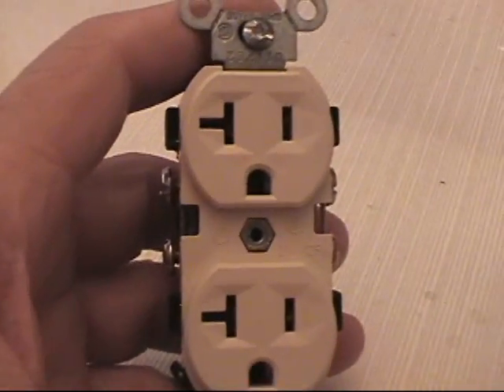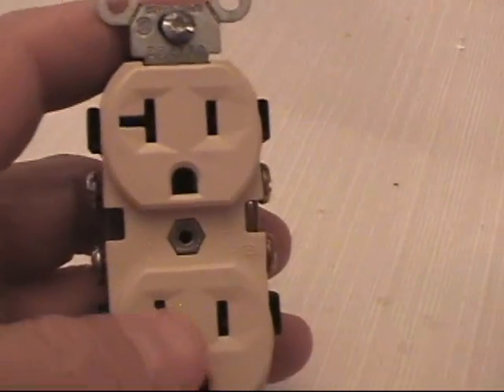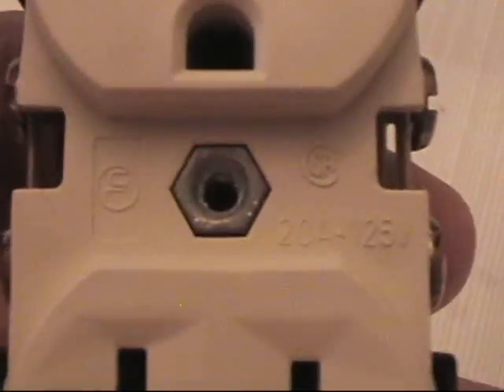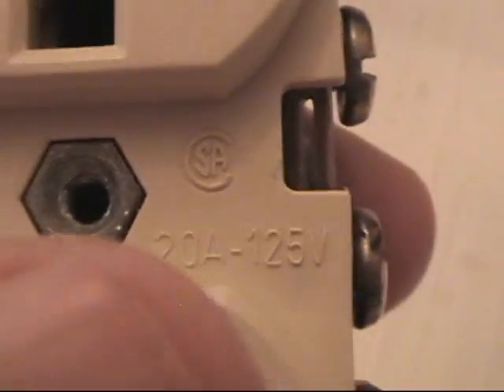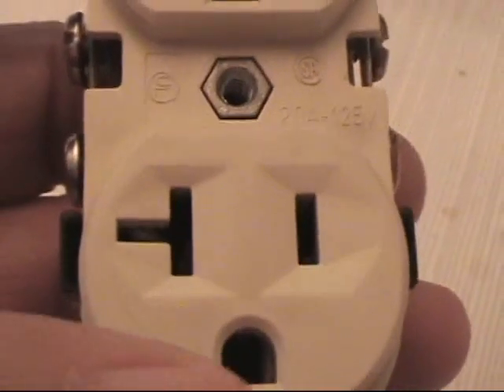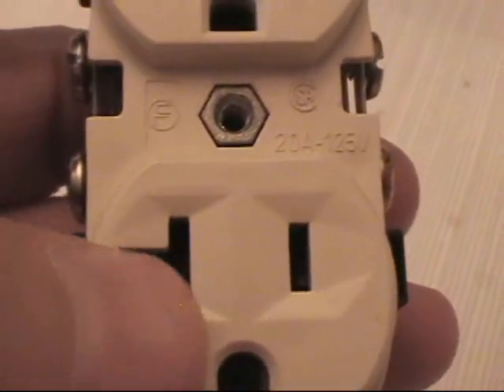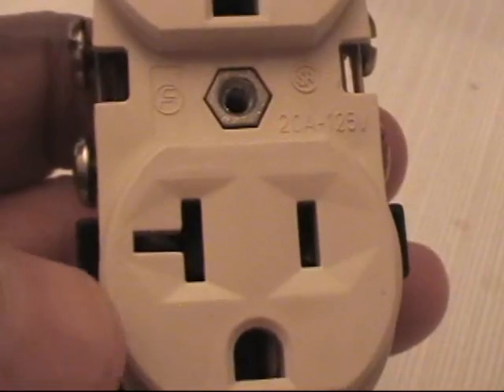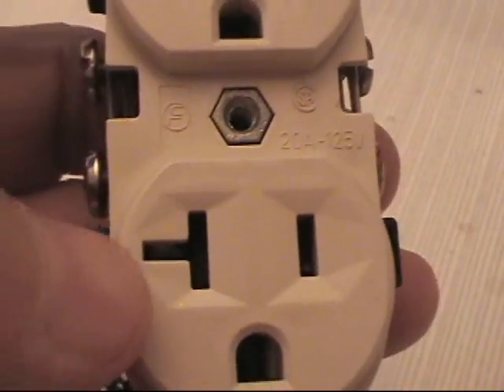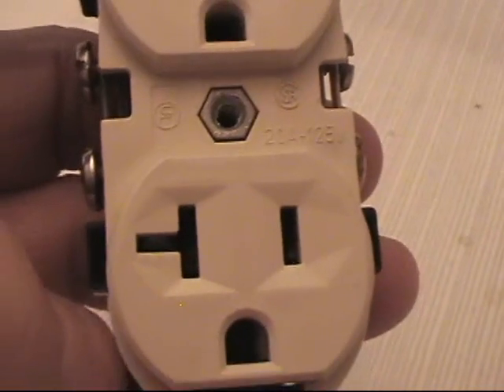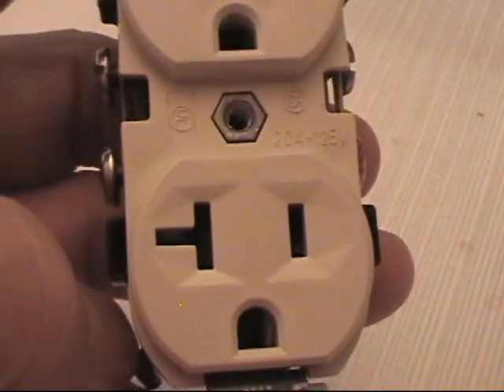Now, this is your standard duplex outlet. This particular one is a 20 amp. It's marked right there. But if you're not sure, and for some reason it may not be marked, you can tell it's a 20 amp outlet because you see this little T on the side, on the ground side here, the neutral side. When you see that, that tells you it's a 20 amp outlet.